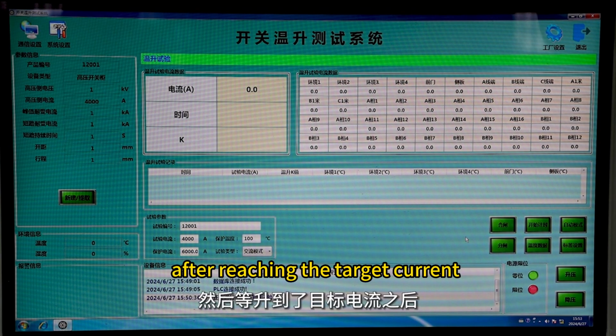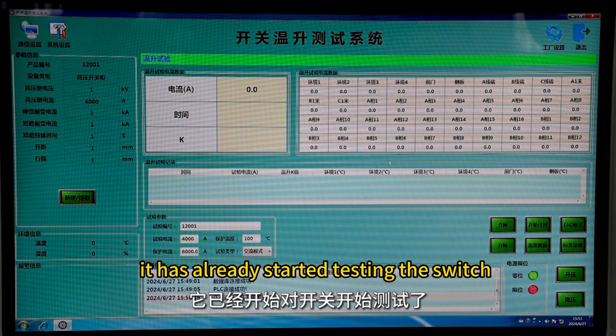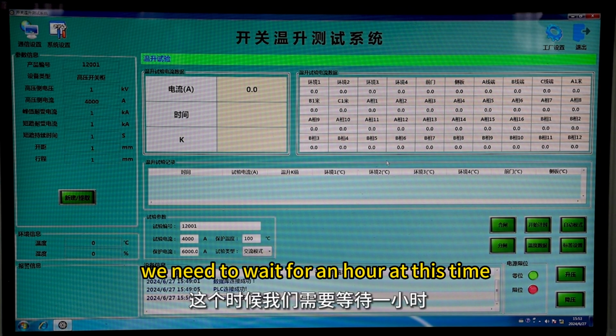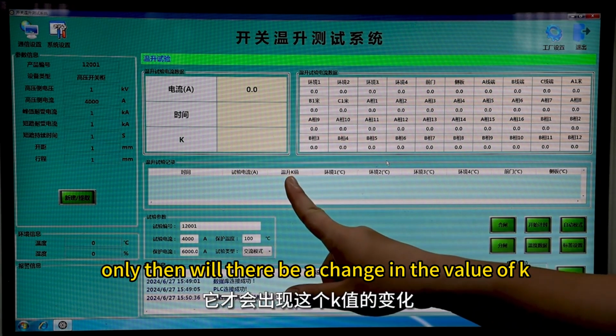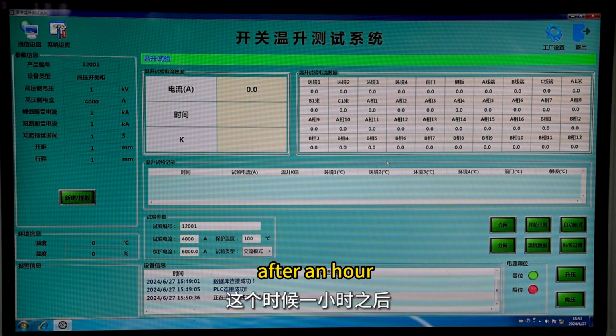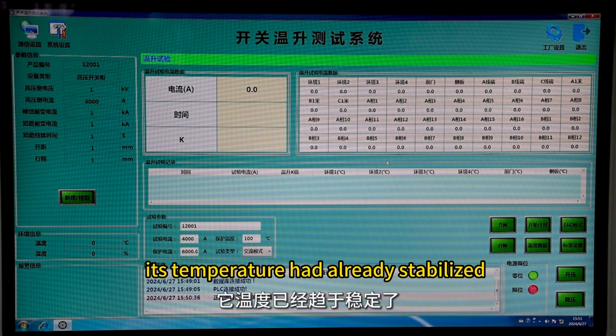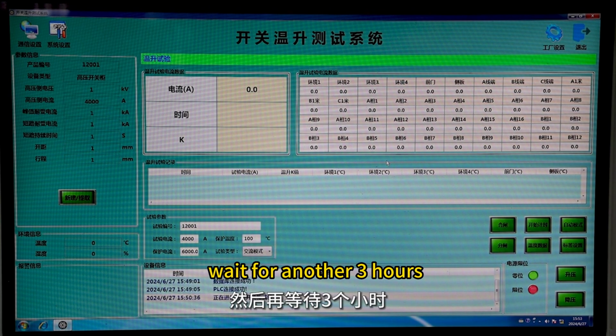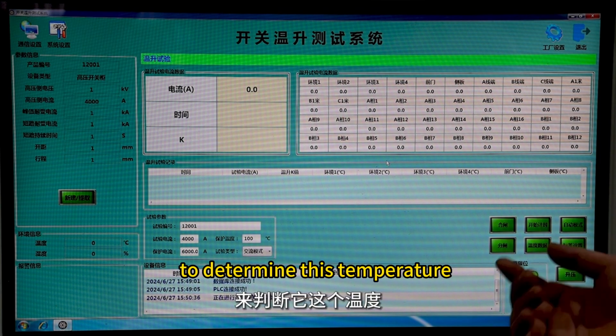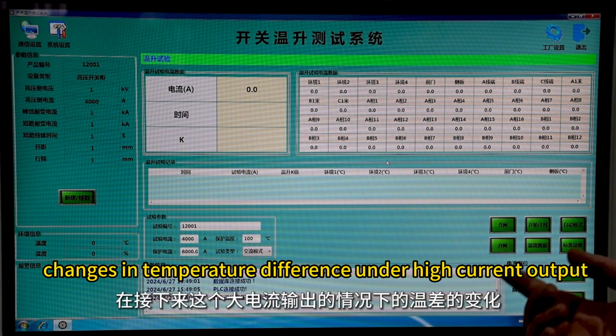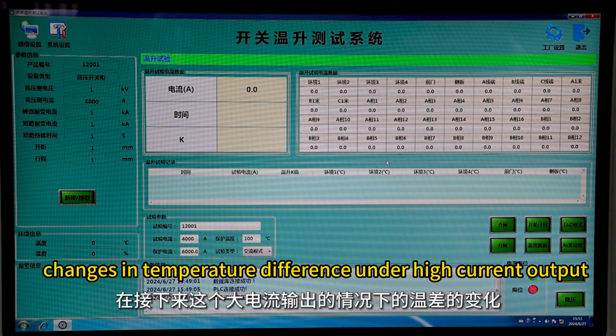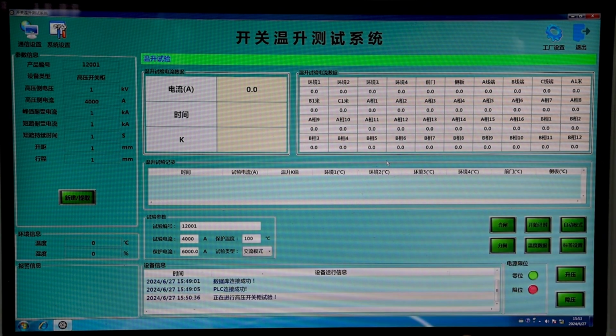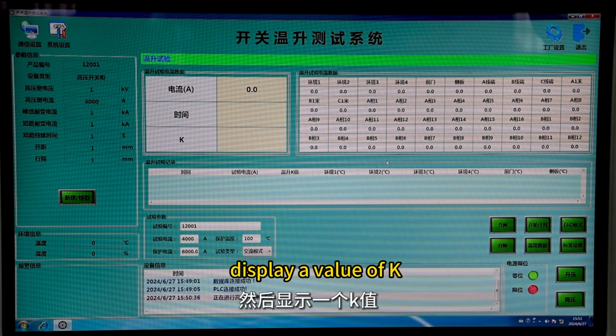After reaching the target current, it has already started testing the switch. We need to wait for an hour at this time. Only then will there be a change in the value of K. After an hour, its temperature has stabilized. Wait for another 3 hours to determine this temperature change, the temperature difference under high current output. Then it displays a value of K.